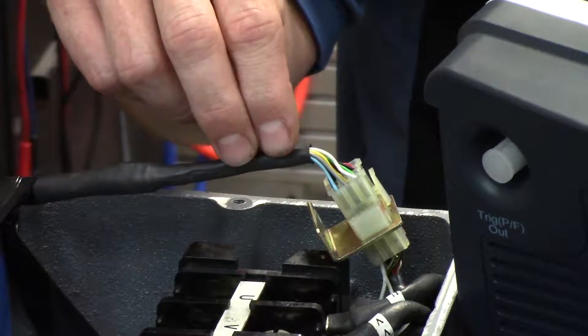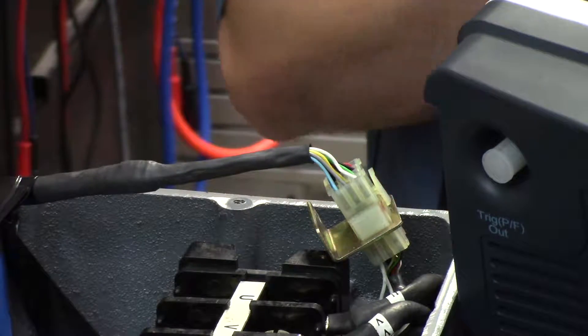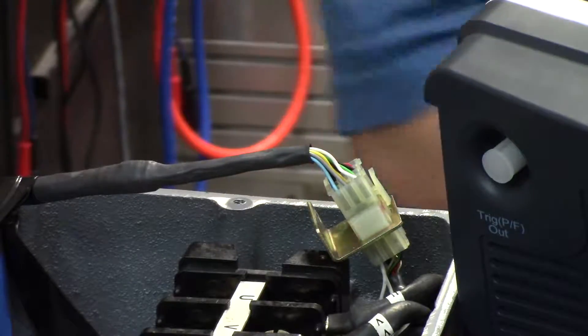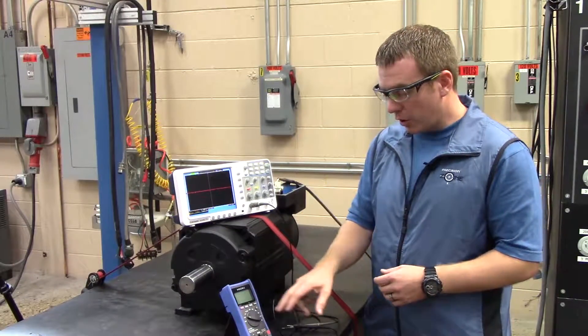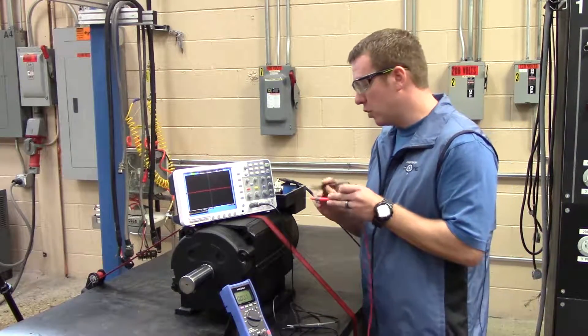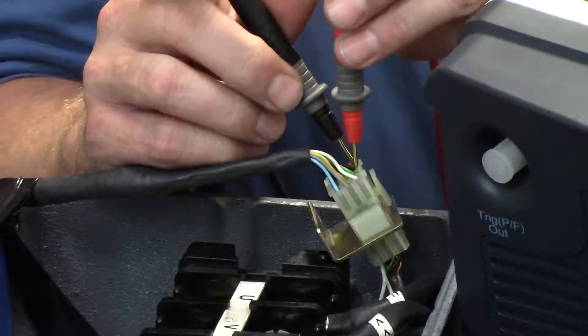Now when you have that all set, you're going to turn on your machine and you can verify that you have power to your encoder by taking a digital multimeter, turning it to the DC setting and checking between pin 1 and 2 and we have 5 volts.